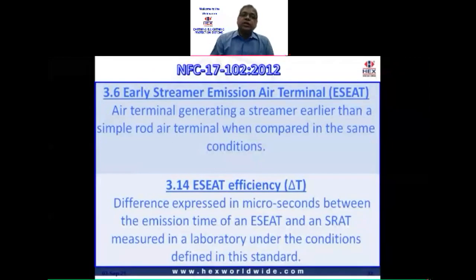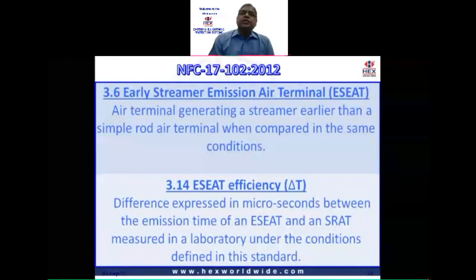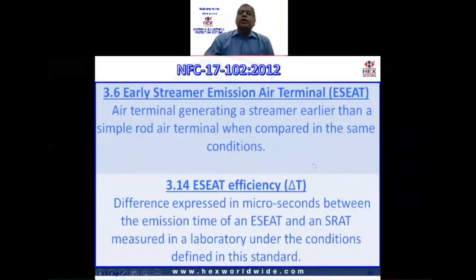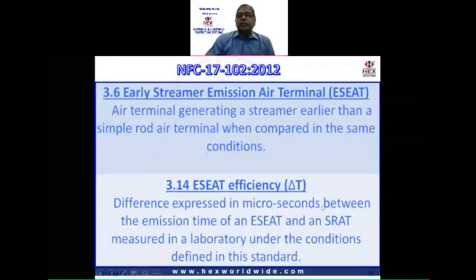Now let's move on to the early streamer emission terminals. Let us see what the NFC 17 standard states. What exactly is an early streamer emission air terminal? It simply defines the ESE as an air terminal that generates a streamer earlier than a simple rod air terminal when compared in the same conditions. The difference in streamer emission time between the ESE air terminal and the simple rod air terminal, measured in the lab under the same conditions, is expressed in microseconds, and it is called delta T.